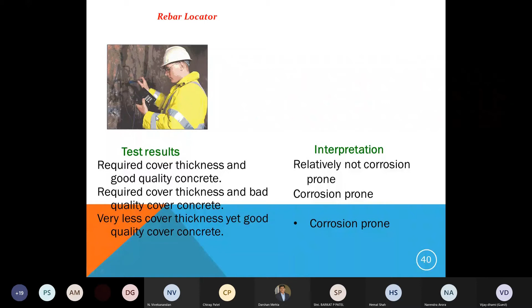So this is a table from which you can understand the required cover thickness and good quality concrete. It's relatively not corroding or has very low corrosion. With the required cover thickness and bad quality cover of the concrete, it is prone to corrosion. If your concrete cover is very little, then as we discussed, it's very high corrosion prone concrete. So using this rebar locator, you can identify the condition of the concrete.